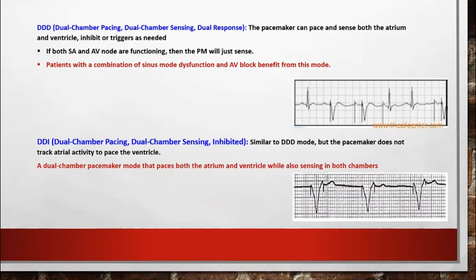Then the dual chamber pacing, dual chamber sensing, and inhibited. So similar to the DDD as discussed in the first one, but the pacemaker does not track atrial activity to pace the ventricle. It is a dual chamber pacemaker mode that paces both atria and ventricles while also sensing both chambers.